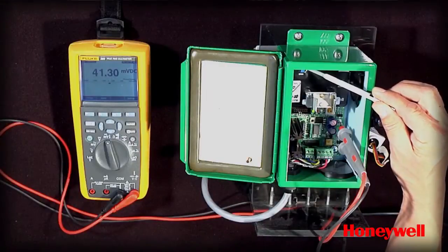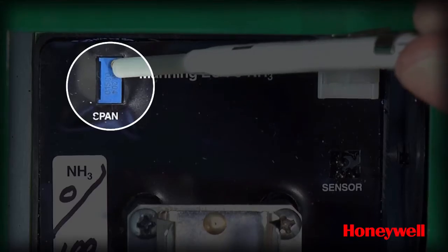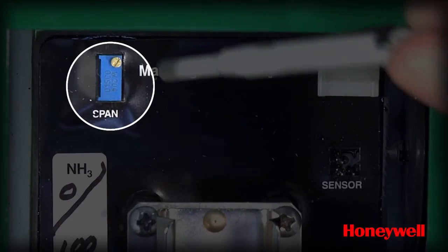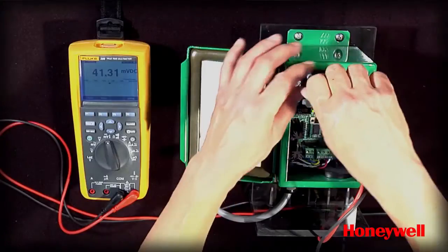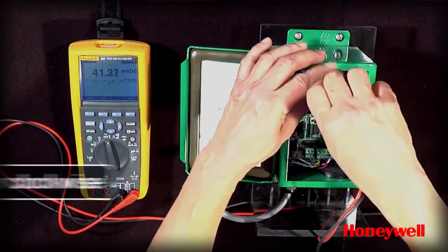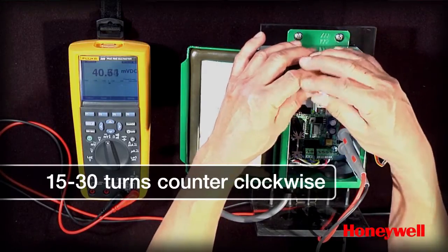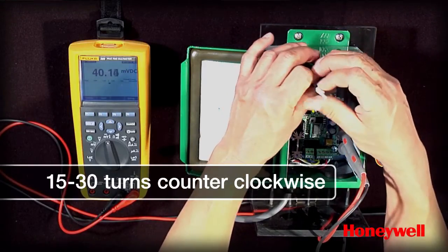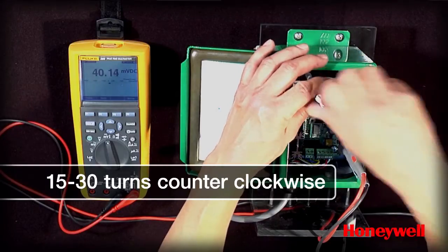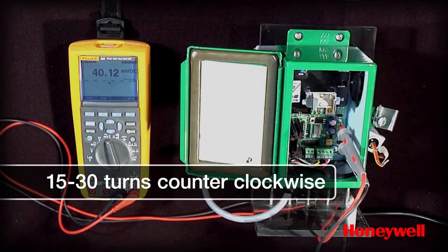The next step in the procedure is to adjust the gain pot, located in the upper left of the board. Using a tuning screwdriver, you want to turn the potentiometer counterclockwise 15 to 30 times, or until you hear a faint clicking. If your unit doesn't produce a clicking, just take care to count out about 30 turns.